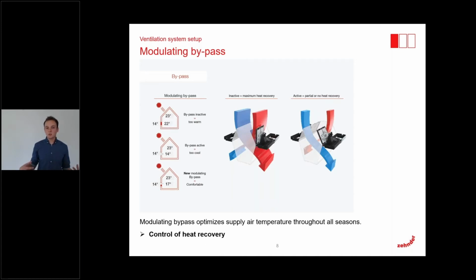So from time to time it gets too warm, our house is getting overheated. So if we open the bypass completely, which is nothing else than just opening the window, except for the filters which we use in our ventilation units, what you get then is a supply air on the same temperature level as the outside air. So then we would take in the air at a temperature of 14 degrees and it will be too cool.